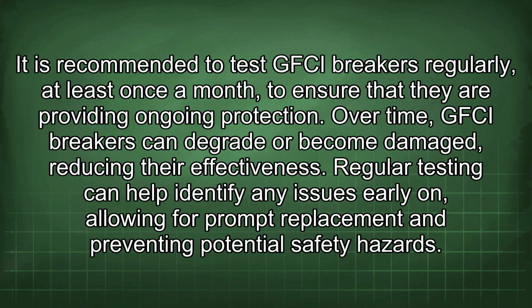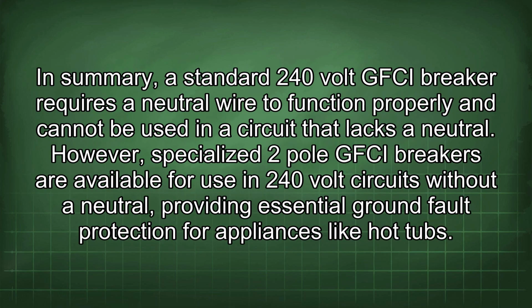It is recommended to test GFCI breakers regularly, at least once a month, to ensure that they are providing ongoing protection. Over time, GFCI breakers can degrade or become damaged, reducing their effectiveness. Regular testing can help identify any issues early on, allowing for prompt replacement and preventing potential safety hazards. In summary, a standard 240-volt GFCI breaker requires a neutral wire to function properly and cannot be used in a circuit that lacks a neutral.